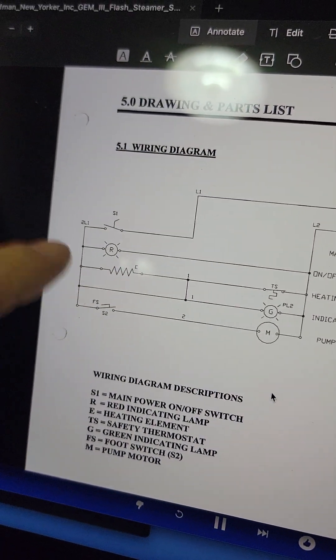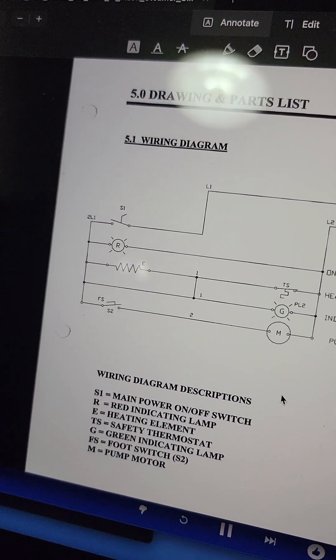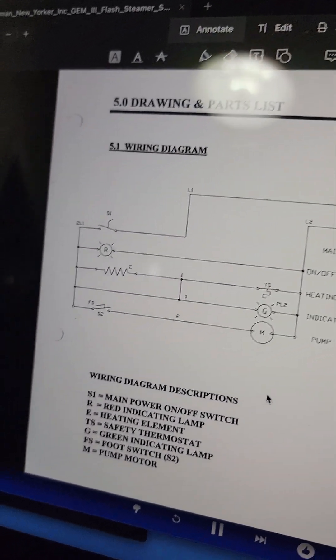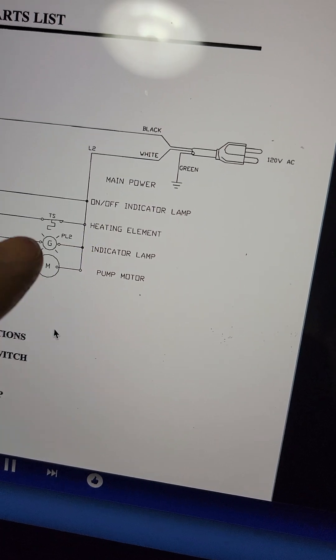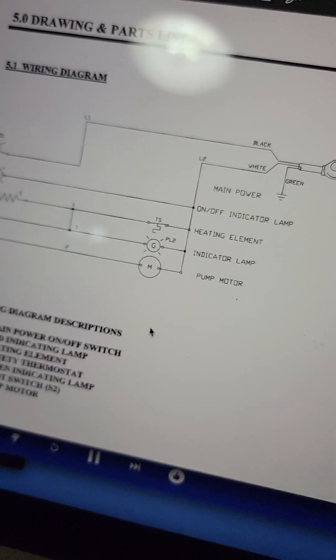The people that made the schematic - I don't know, maybe they're drunk - this resistor-looking symbol here is a heater. FS is foot switch (switch 2), M for motor (pump motor), and there's your lines just going around. Right here is the wiring diagram description of what each thing is.